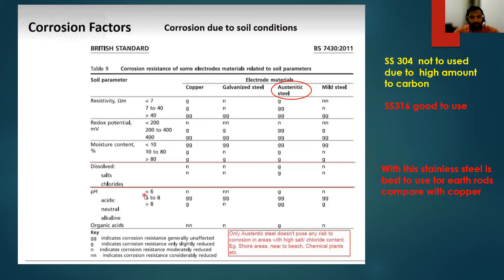Copper will be N if less than 6. If the earth resistance is acidic nature less than 6, N for copper, galvanized is N, austenitic steel is G which is better, and mild steel N. For 6 to 8, everything is good because this 6 to 8 is a normal condition. Greater than 8, then copper is good, galvanized is little good, austenitic steel is very good (GG), and mild steel also good.